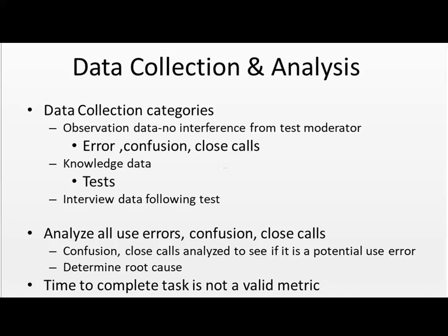You should analyze all use errors, confusions, close calls. You don't want to restrict your analysis to the errors, failures, and determine the root cause for all errors, confusions, close calls.